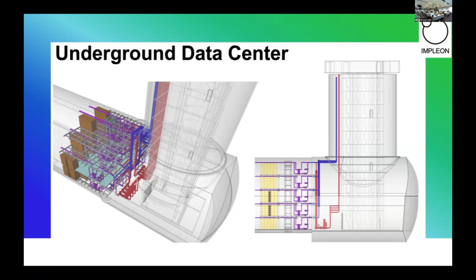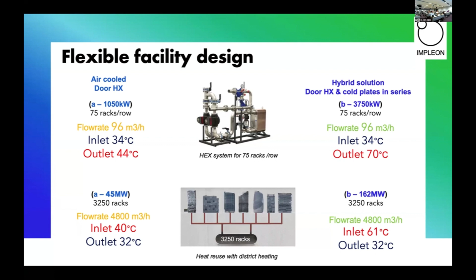The idea is to create a flexible design. You can fill it with air-cooled racks at 14 kilowatts each, giving 1 megawatt for 75 racks, or shift to liquid cooling with the same flow rate but a capacity of 3.7 megawatts. Overall, you can shift from 45 megawatts to 162 megawatts without any changes in infrastructure—same heat exchanger, same pumps, same control valves, everything the same. The difference is only in temperatures.